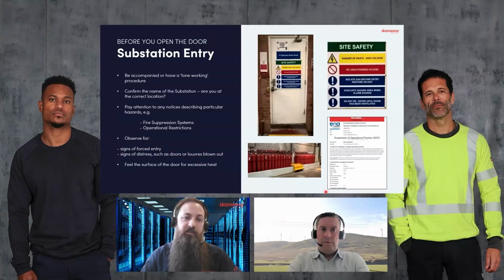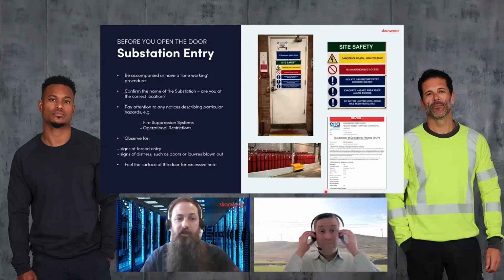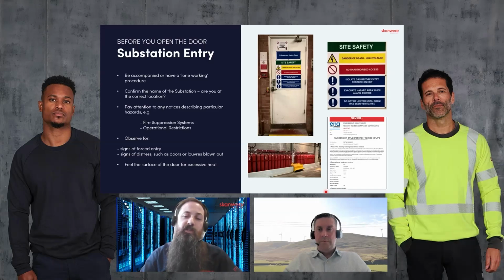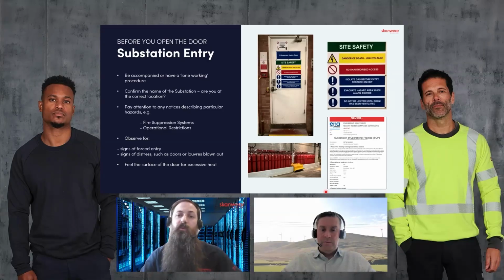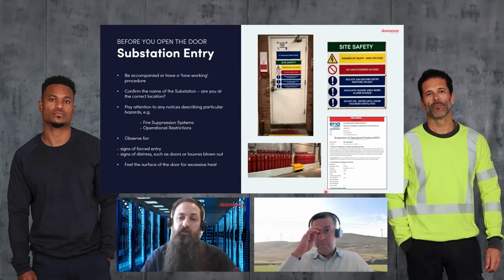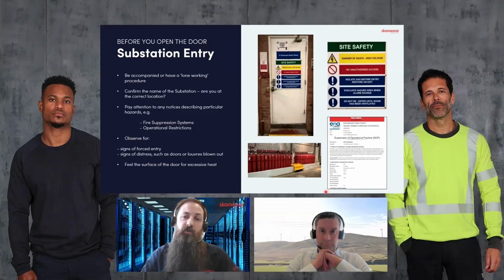Pay attention to any hazards: signage on the door, fire suppression systems, and operational restrictions that might impact how you enter a space. There's a certain type of switchgear at the moment with an operational restriction linked to partial discharge. When you get to the compartment, you do a partial discharge survey from the door, and if you're not picking anything up, you then do a full PD survey of the gear before continuing. So it's important to know about any operational restrictions to make sure you're safe when entering.